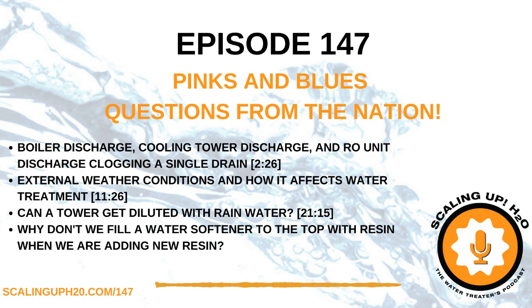Well, the issue is there needs to be more than just resin in that tank. We have to account for the water that goes into that tank. Now, specifically, we need enough space to fluff up that resin when it's being backwashed. So if you're not familiar with the term backwash, backwash is the first step in the regeneration cycle of a water softener. Now, if you're not familiar with the regeneration process of a water softener, let me try to refresh your memory on that. A water softener is used to take hardness out of the water, specifically calcium and magnesium. Our goal is not to create scale within the system or maybe making it easier for soap to lather, depending on what industry you're in.